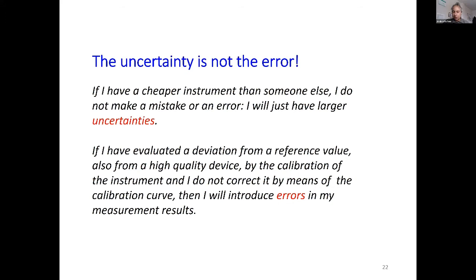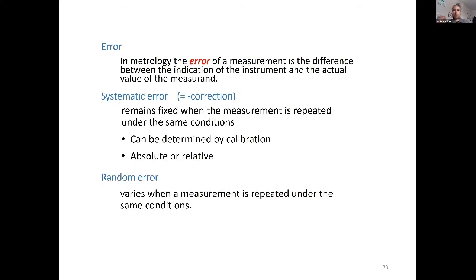If I have evaluated a deviation from a reference value, also from a high quality device, by the calibration of the instrument, and I do not correct it, then I will introduce errors. The error in metrology is the difference between the indication and the actual value of the measurement. We have to correct errors. If I have an error and I know this number, I have to take it out of my instrument reading. Don't leave instruments with error.